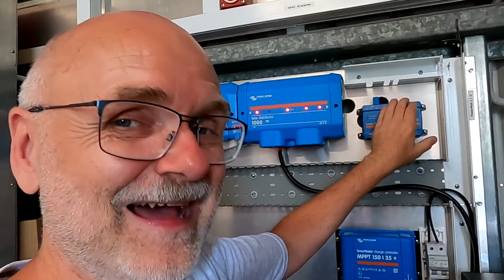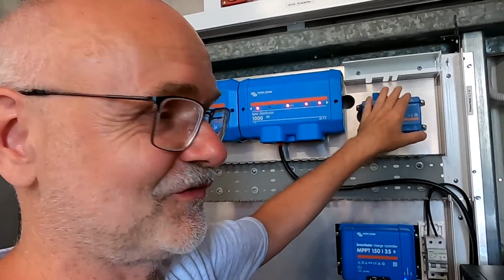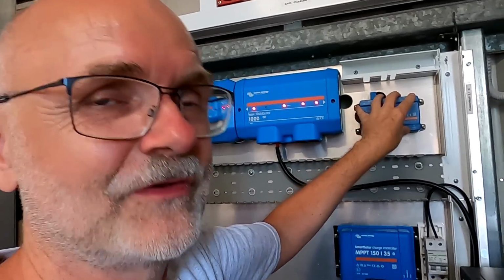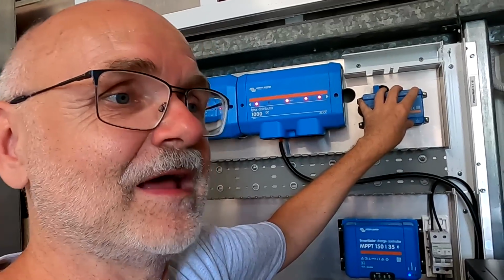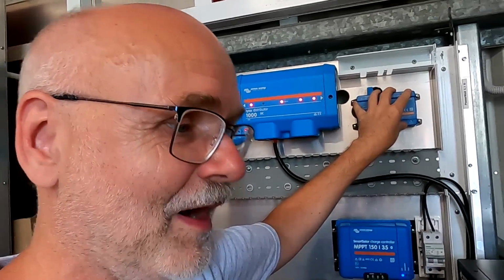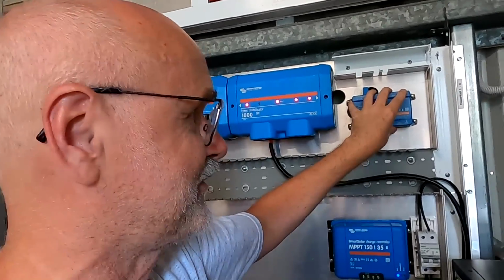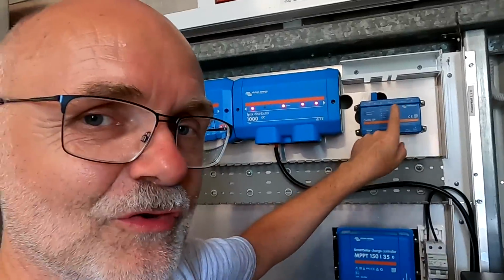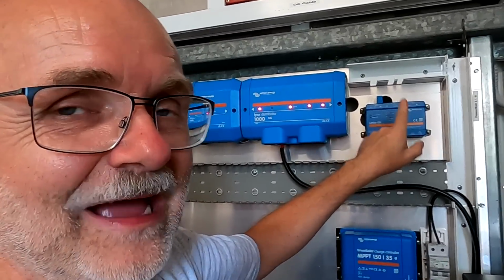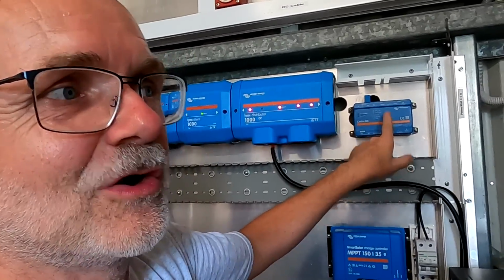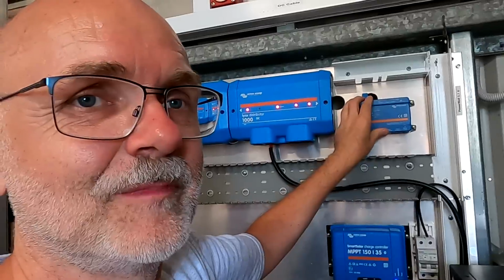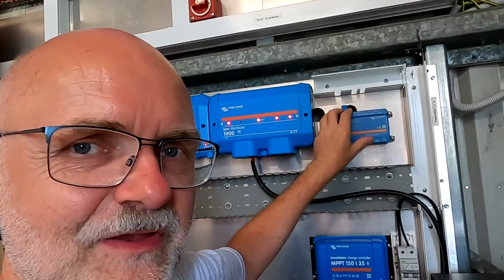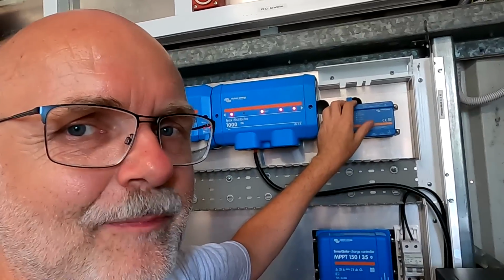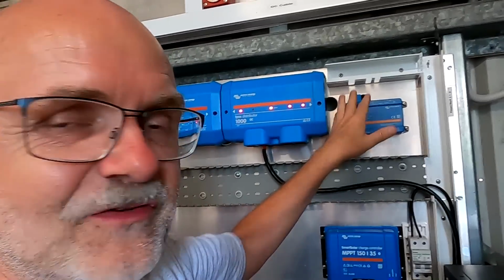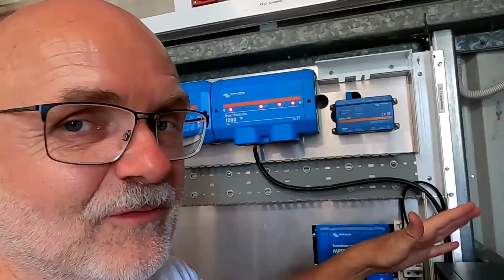This is probably the last thing you actually want, because you want this one up and running all the time, so you can have a look at the data and see what was going on, why did you get a fault, what was the cause of it. So I want to connect this one either to a different power supply or to a kind of UPS system where we can use a bunch of 18650 cells or something to keep this one up and running until we did all the troubleshooting in case of a fault.